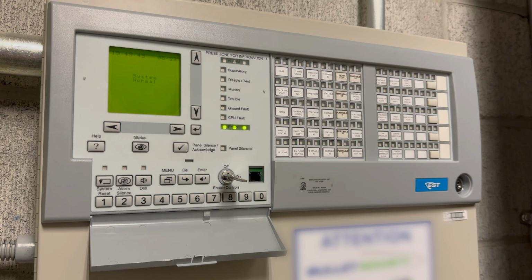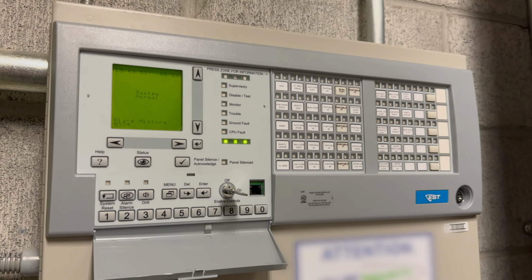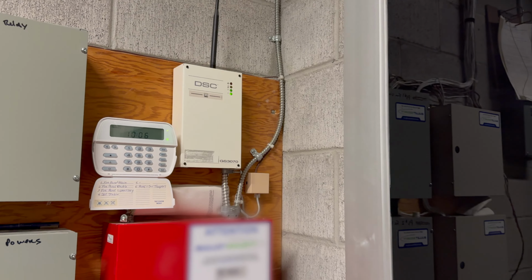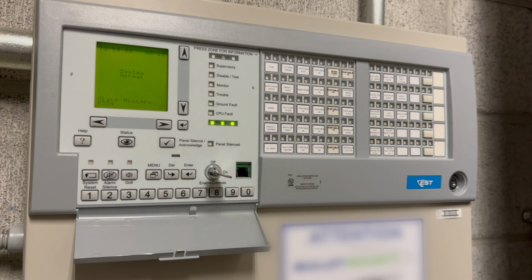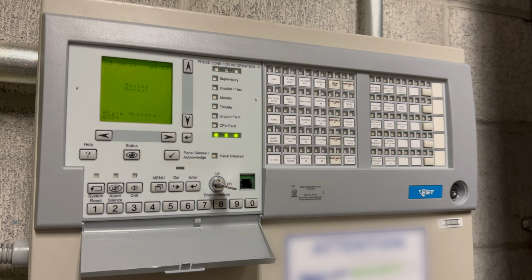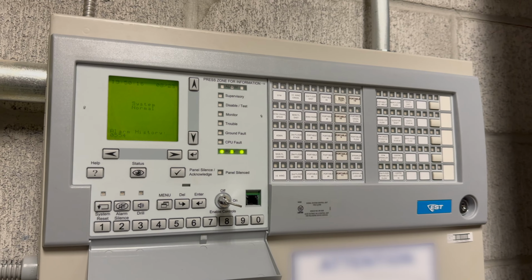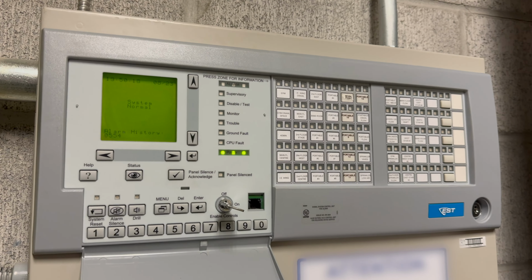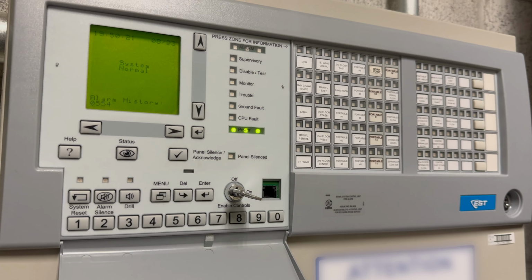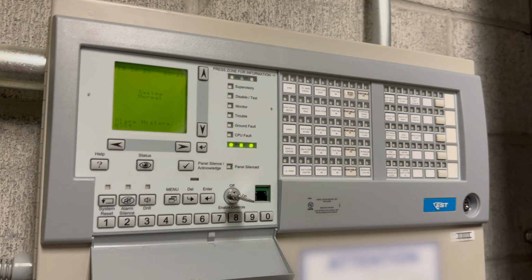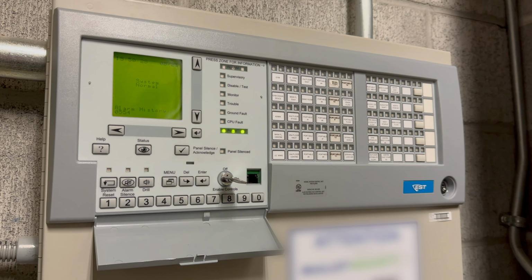This is just one that's a little bit easier to show, and some of them are only monitored for alarm. This one is a proper ULC listed setup where we actually have the separate panel like required, as well as wireless. So we have our two forms of communication. So we're going to be testing this one for all three conditions. We'll call the monitoring company, put it on test, and unfortunately they won't stay on the phone with us. So we have to do everything at the time and record what time we set things off and then call back and check. So we'll check this for alarm and trouble and supervisory because this system actually has all three. So it's a little bit more interesting to show this one.